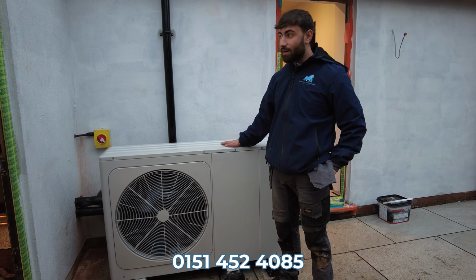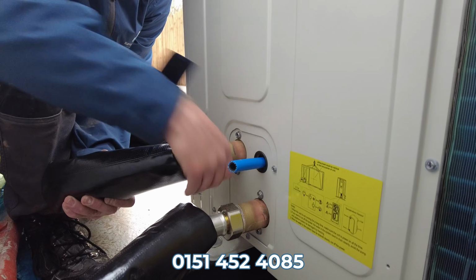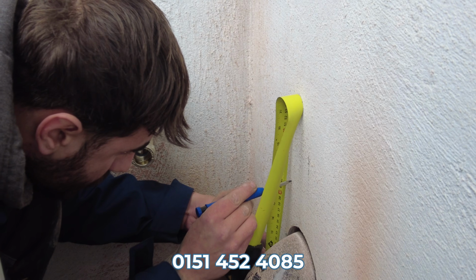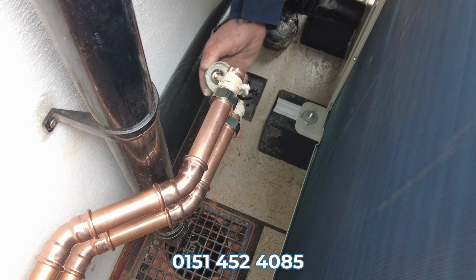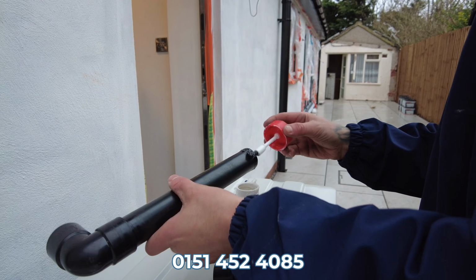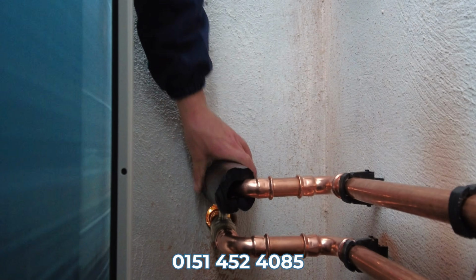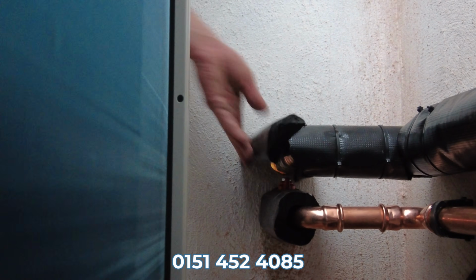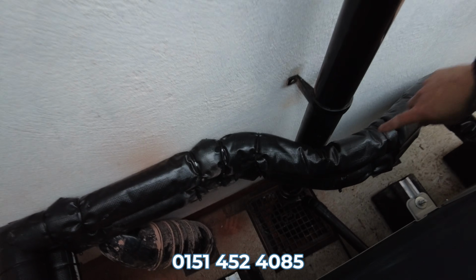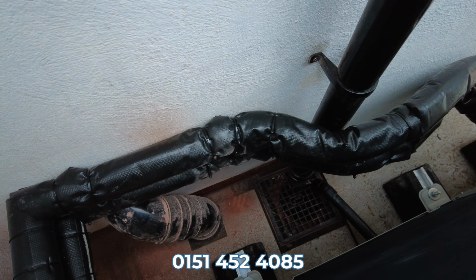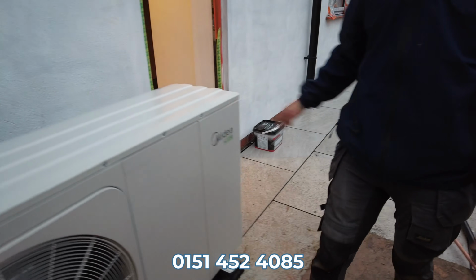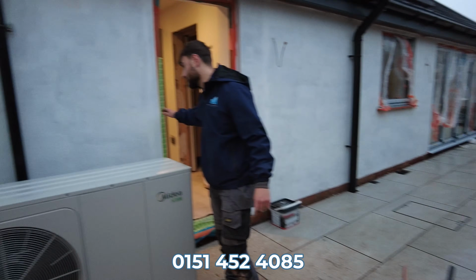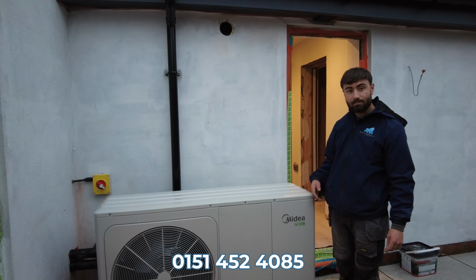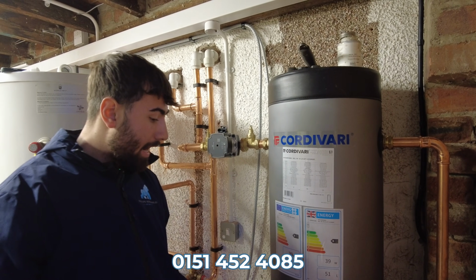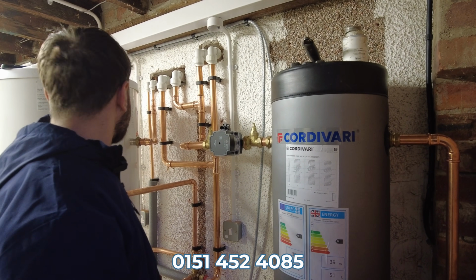Right, everything outside is now completed, the heat pump's in place. All the pipes have been insulated with a UVC lagging. We've got some valves there if it needs shutting off. We've also got a condense pipe that goes straight into a drain, and that is everything outside. Heat pumps on the feet with the right measurements from the wall. And that's outside.